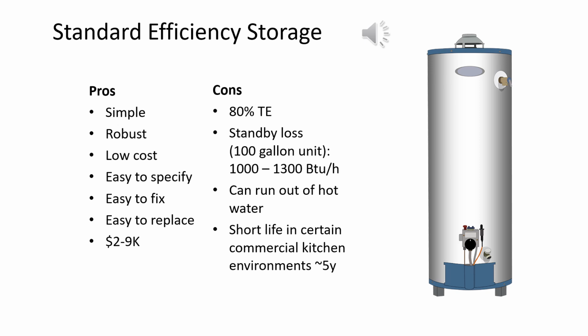The most common water heater type is the standard efficiency natural gas fed storage water heater. The pros of this are that these heaters are very simple, they're robust, they're low cost, they're easy to specify, easy to fix, easy to replace, and relatively cheap with an upfront cost of between $2,000 and $9,000 depending on the size of the heater and how much storage it has. The cons are that it only has an 80% thermal efficiency, they can have significant standby losses, they can run out of hot water, especially if they're undersized, and they have a short lifespan in commercial kitchen environments around 5 years.